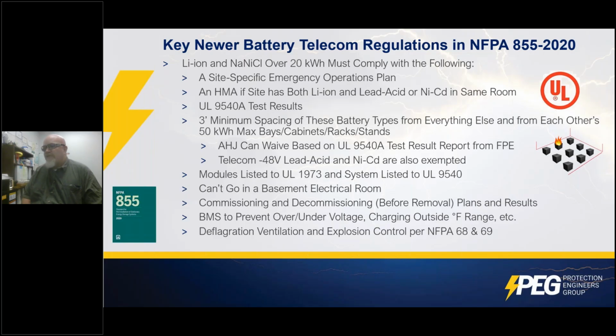That's what that little picture over there to the right shows. The AHJ can waive that based on the 9540A testing that's been done and a report written by a fire protection engineer that convinces them that these are not likely to spread. However, many lithium-ion batteries are likely to spread, so that's why they often go in outdoor containers when they get into larger sizes. Telecom 48-volt lead acid and NiCad are exempted from that spacing. Modules have to be listed to UL 1973, and systems have to be listed to UL 9540 for your lithium-ion, sorry, not your NiCad. They have to have that listing, whereas lead acid doesn't.